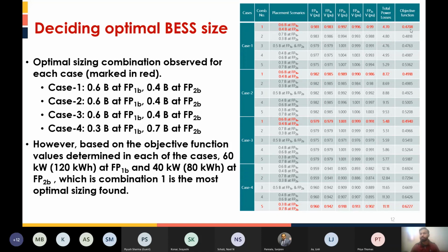As the maximum number of times the objective function is minimum is in case 1, we considered the optimal placement and sizing as the case 1 placement combination scenario: 60% battery on feeder pillar 1B and 40% battery on feeder pillar 2B.